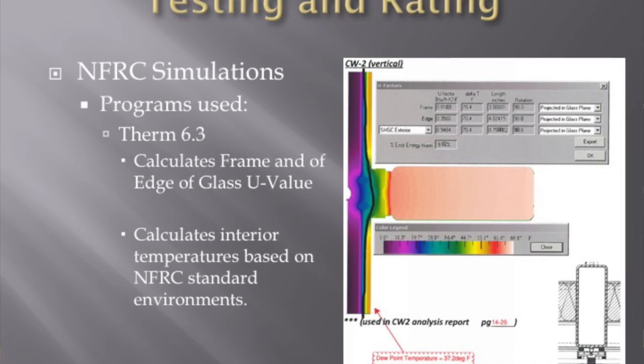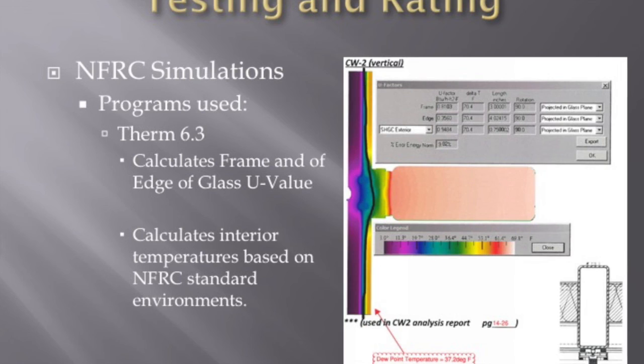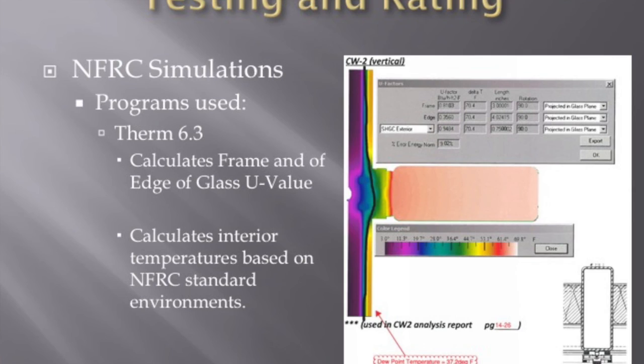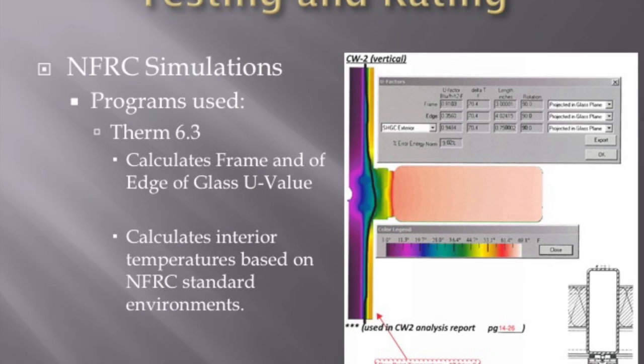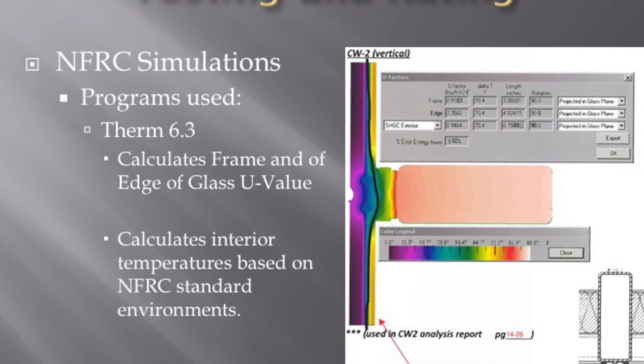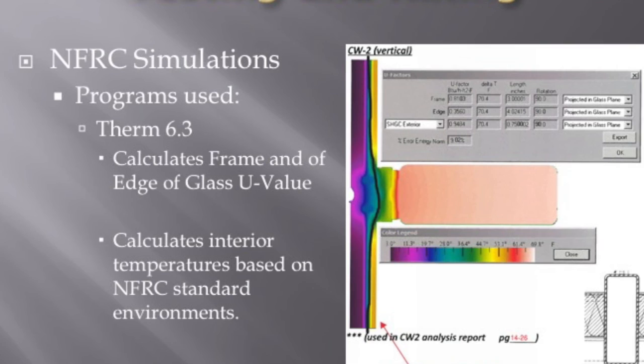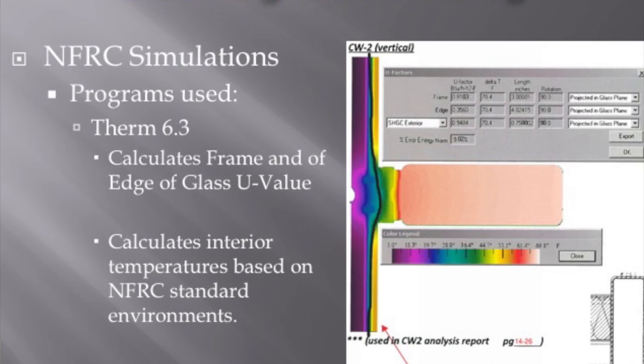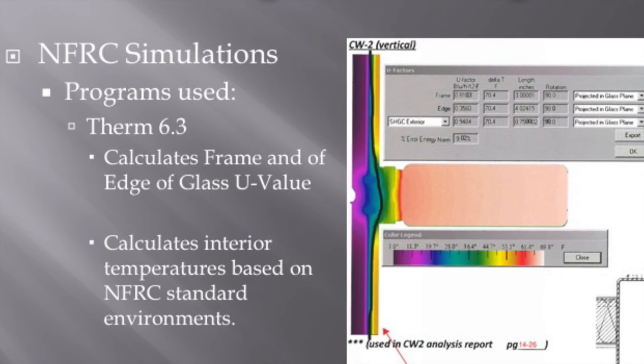Therm 6.3 calculates edge-of-glass and frame thermal properties. You take all the important cross-sections from your curtain wall system, plug each one into the program, and it calculates the U-factor for each section along with an interior temperature based on your interior and exterior environment conditions. Therm is a 2D heat analysis program — that's essentially all it can do, but it's very effective for that purpose.